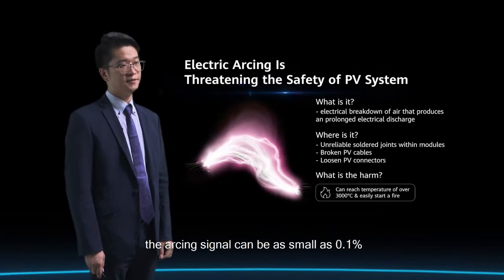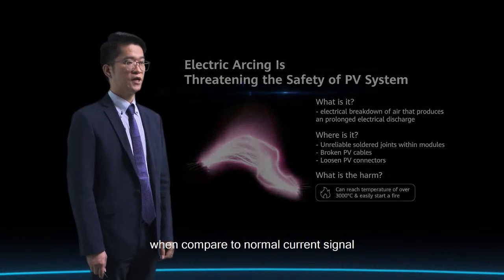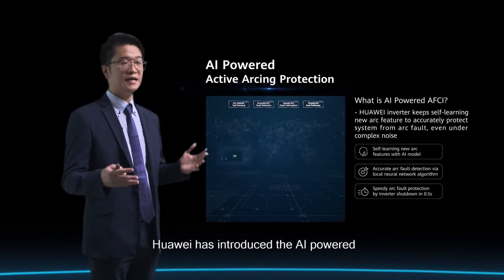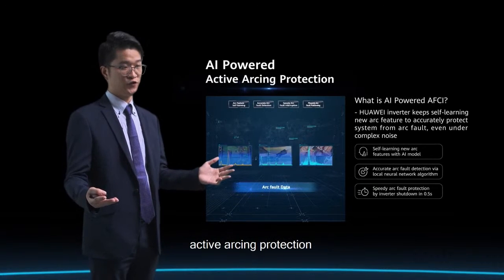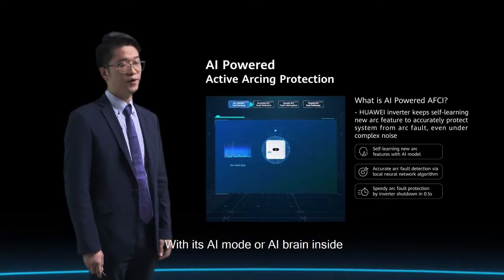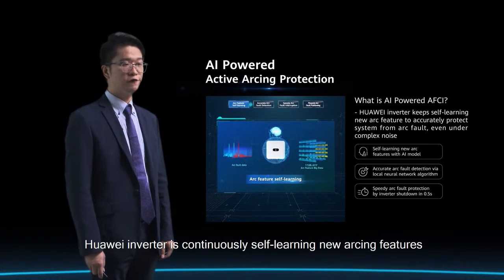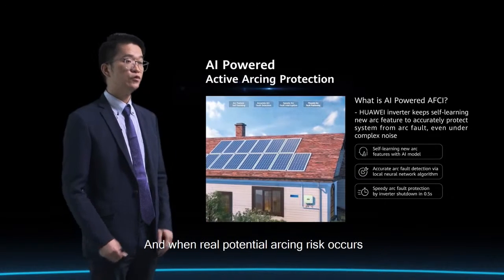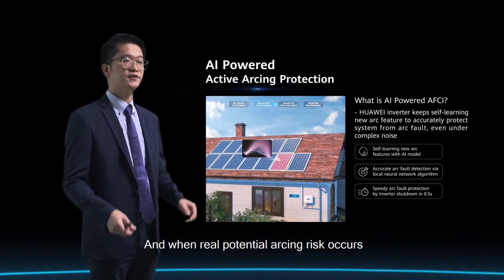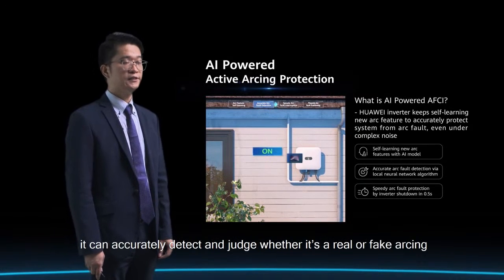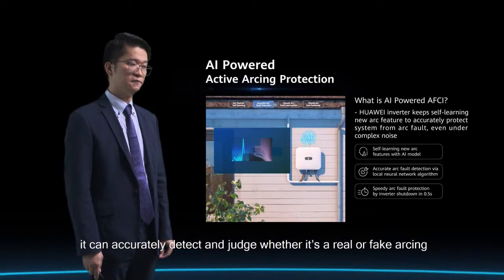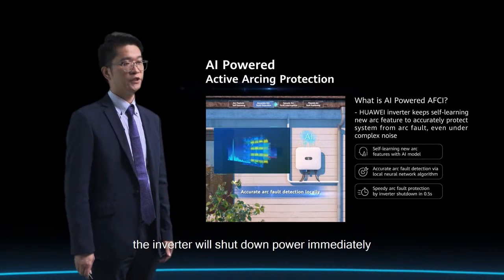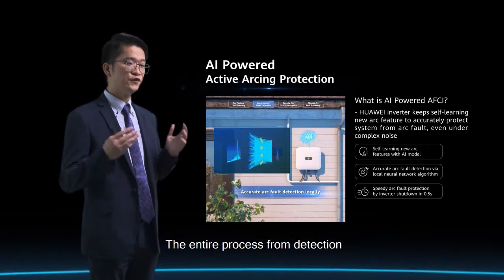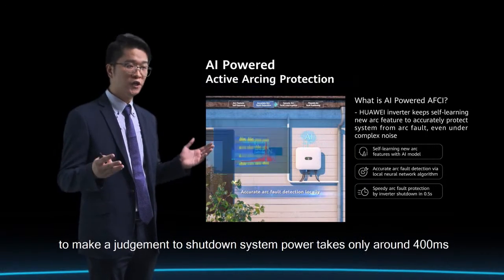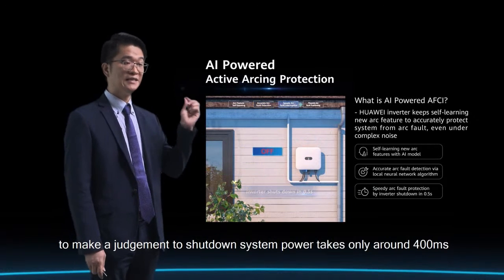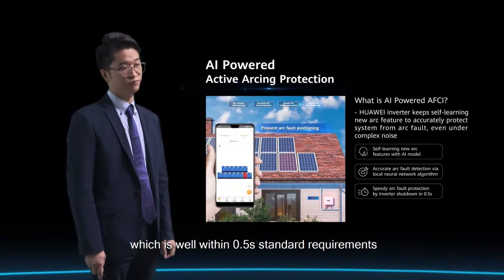The arcing signal can be as small as 0.1% when compared to normal current signal. And for this challenge, Huawei has introduced the AI-powered active arcing protection. With this AI model, or AI brain inside, Huawei inverter is continuously self-learning new arcing features. And when real potential arcing risks occur, via its local neural network algorithm, it can accurately detect and judge whether it's real or fake arcing. And if it's real arcing, the inverter will shut down immediately. The entire process from detection to make a judgment to shut down the system power takes only around 400 milliseconds, which is well within the 0.5 second standard requirements.